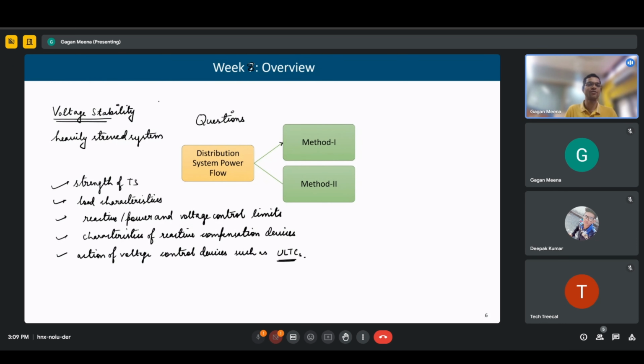So I was just telling that the voltage stability problem occurs when the system is heavily loaded or heavily stressed. Several factors determine this voltage stability issue, such as the strength of the transmission and distribution system, the load characteristics and its value, and different reactive power compensation devices placed within the system, and how these components work, such as on-load tap changing transformers. When the voltage reduces, the taps of the transformer need to be changed to maintain the voltage. So all these things determine the voltage stability.